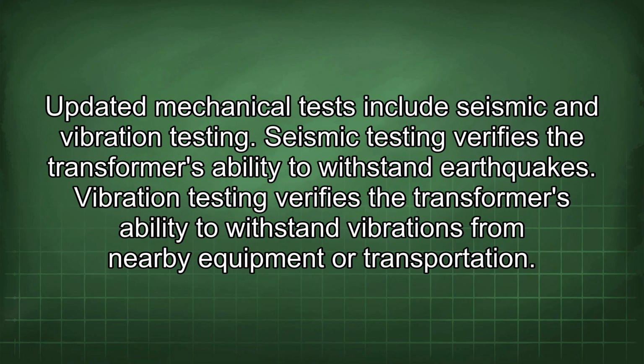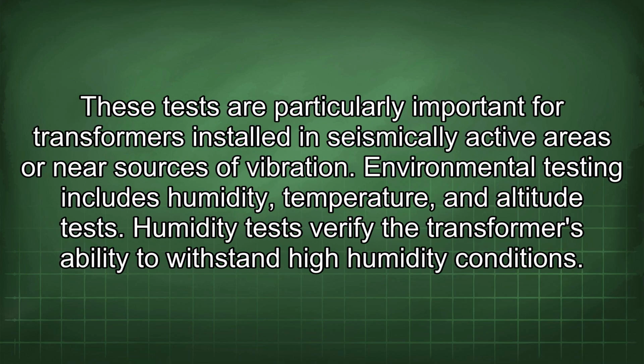Updated mechanical tests include seismic and vibration testing. Seismic testing verifies the transformer's ability to withstand earthquakes. Vibration testing verifies the transformer's ability to withstand vibrations from nearby equipment or transportation. These tests are particularly important for transformers installed in seismically active areas or near sources of vibration.